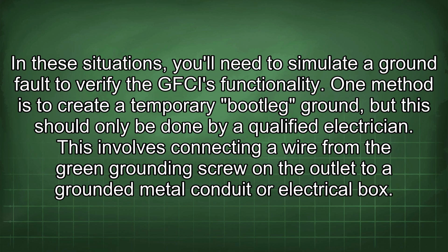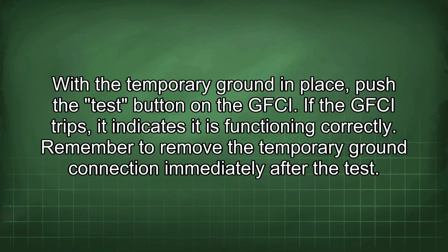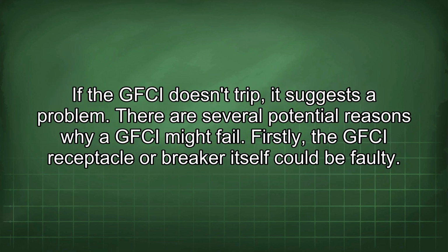One method is to create a temporary bootleg ground, but this should only be done by a qualified electrician. This involves connecting a wire from the green grounding screw in the outlet to a grounded metal conduit or electrical box. With the temporary ground in place, push the test button on the GFCI. If the GFCI trips, it indicates it is functioning correctly. Remember to remove the temporary ground connection immediately after the test. If the GFCI doesn't trip, it suggests a problem.